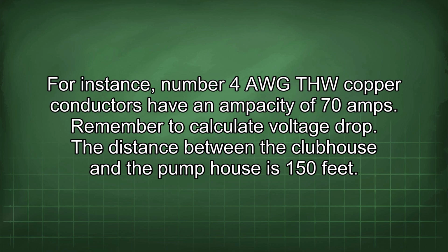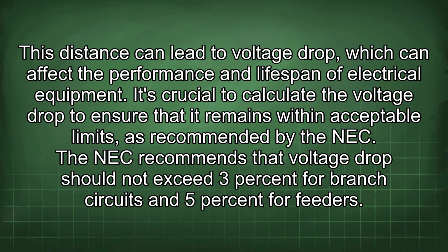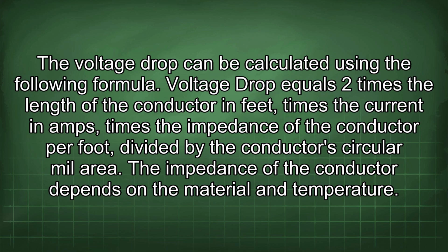The distance between the clubhouse and the pump house is 150 feet. This distance can lead to voltage drop, which can affect the performance and lifespan of electrical equipment. It's crucial to calculate the voltage drop to ensure that it remains within acceptable limits, as recommended by the NEC. The NEC recommends that voltage drop should not exceed 3% for branch circuits and 5% for feeders. The voltage drop can be calculated using the following formula.